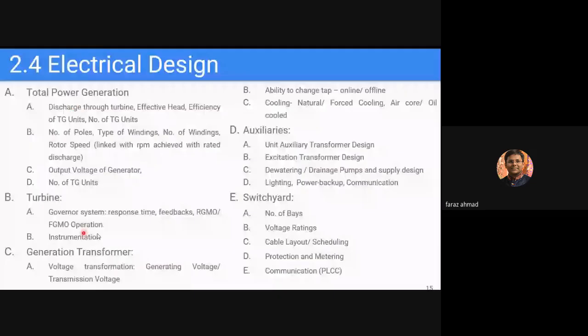Then coming to the turbine, if I'm talking about the governing electrical design, there is a governing system. So how much the gates should be open for a required RPM of the machine, because in grid operation the frequency varies very instantaneously. Within a few milliseconds, you can see variations from 50.00 hertz to 50.01 or 50.02 hertz. Now, in order to match this, since the generators and the whole system have a very large inertia, in order to get a particular response out of the machine, you need to design it accordingly. So that once the grid frequency rises, then accordingly the frequency of our machine should also rise. There are some restrictions on free governor mode operations.